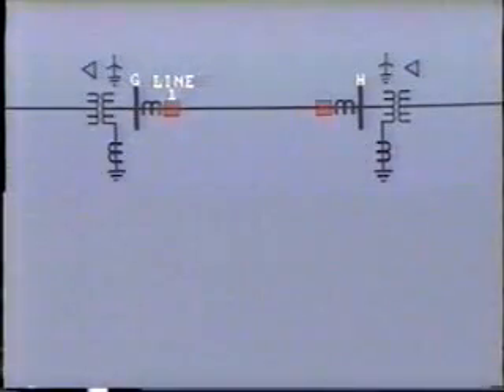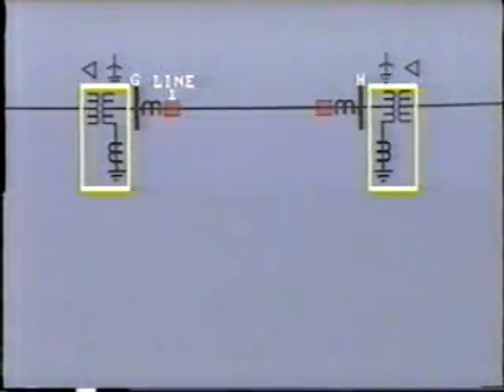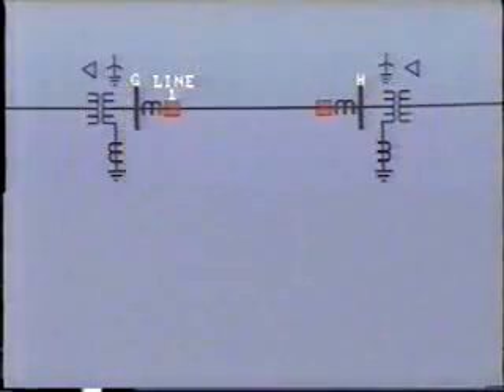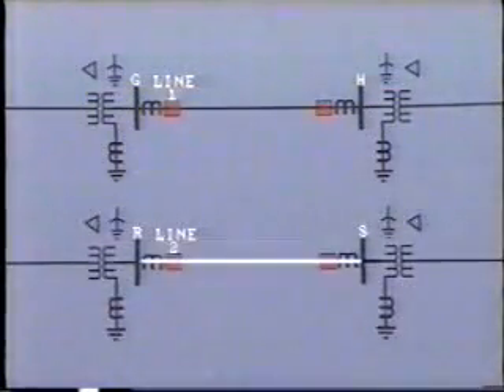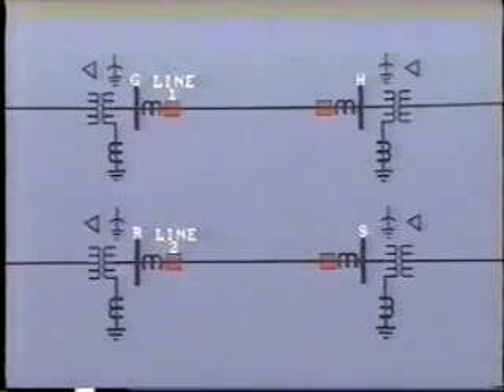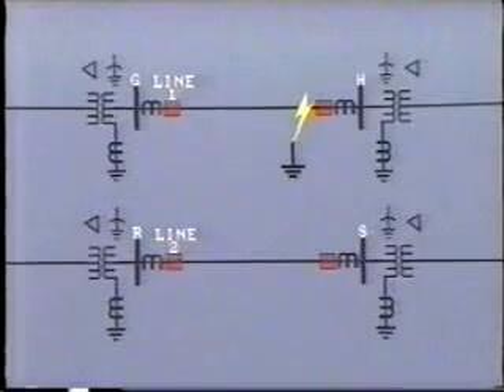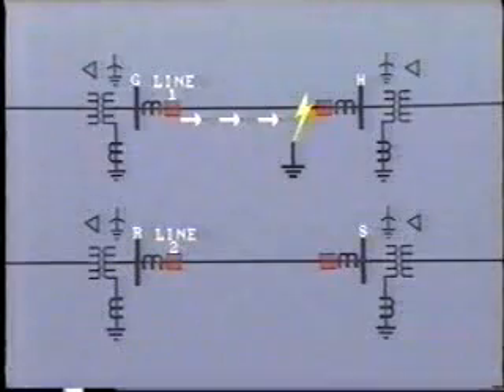Let's look at an example. Line 1 runs between buses G and H. At each end, the buses are connected to the high voltage side of transformers, which are Y-connected with a grounded neutral. Similarly, line 2, which runs in close proximity, is connected between buses R and S. Now let's suppose that there is a ground fault at the far end of line 1, close to bus H. The zero-sequence fault current will run along the line down to the fault, to ground, and up through the neutral at bus G.